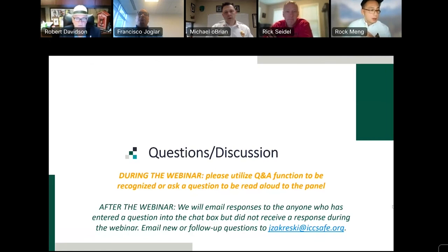Okay, this is Bob Davidson. With the sprinkler requirements, we didn't say install in a sprinkler environment, but all the model codes out there have required even 1 and 2 family homes and dwellings to be sprinkled for new construction for quite some time now. So when we add language to the codes, there's an assumption of buildings in compliance with the code. As far as any changes to 13 or 13D, UL 9540A has large scale testing, right?